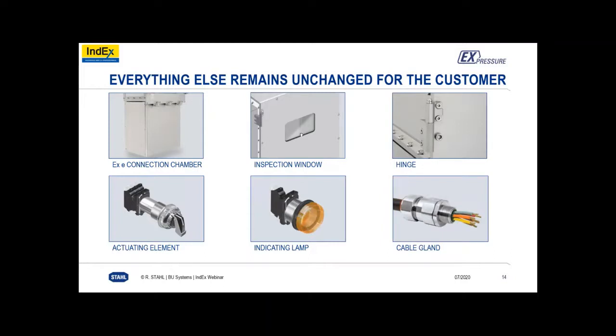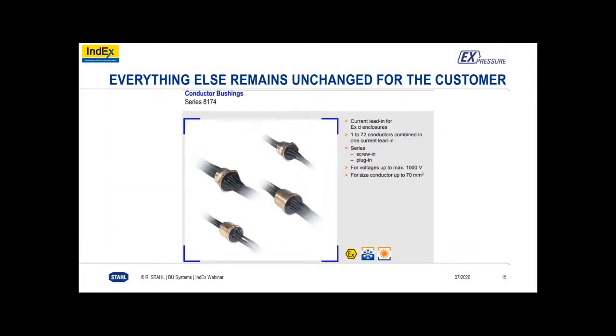It also can be equipped with EXE connection chambers, cover hinges, actuators, rotary drives, and signal lamps, and the standards and rules remain the same for the cable entries and also for the actuators according to -1 and -14. If it's an EXE connection chamber, then the cable gland has to meet -7, -14. So then the use of EXE cable glands is available. Yes, and in the case of an EXE connection chamber, the interface between the EXD and the EXE side is made through so-called conductor bushings, which can be screw-in and plug-in types up to 1000 volts, and we also have some bolt type conductor bushings, which can be used up to 240 square millimeters.